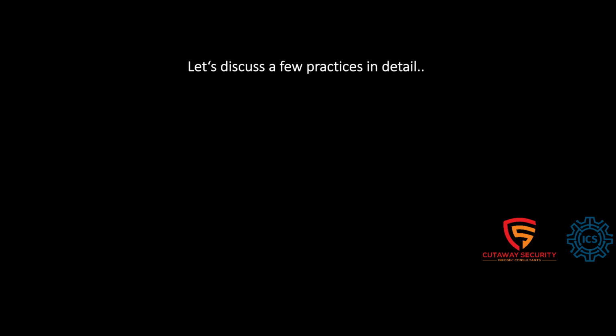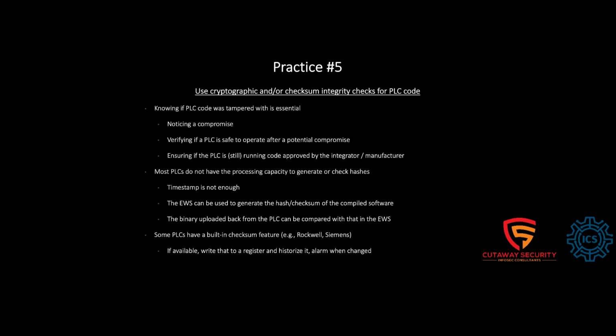So we can discuss a few practices in detail. I took a relatively straightforward one: using cryptographic or checksum integrity checks for the PLC code. Clearly, after a PLC is shut down or something happened, you want to be able to confirm that the code you have in the PLC is good, right? So what is that known good? Whether the PLC code is tampered with or not is essential to confirm, to notice a compromise, for example, and then to verify that the PLC is safe to operate after a potential compromise. And then ensuring that the PLC is still running the code approved by the integrator or the manufacturer, or the one that you signed off after an FAT. So you want to be doubly sure that that's the same code, right?